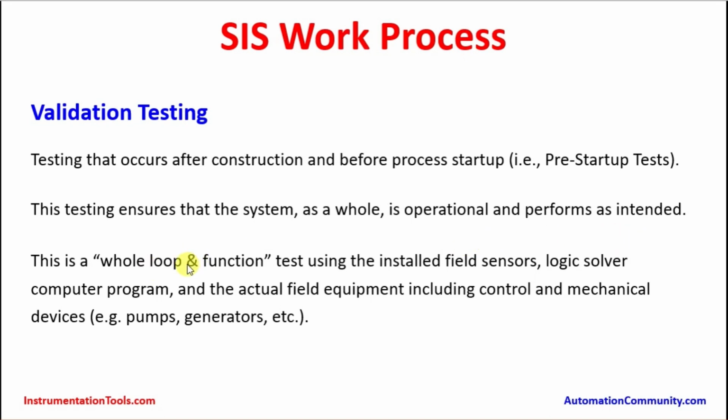This is a whole loop and function test using the installed field sensors, logic solver, computer program, and the actual field equipment, including the control and mechanical devices like pumps, generators, or any turbine, or any other equipment associated with it, or there could be only some on-off valves associated in this safety instrumented system. So this is a complete testing.